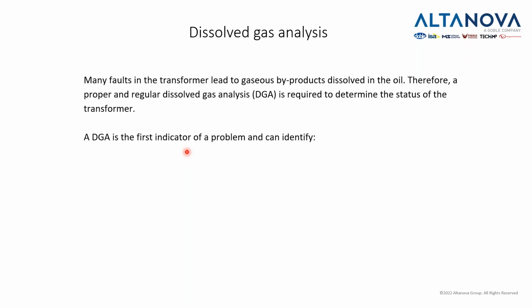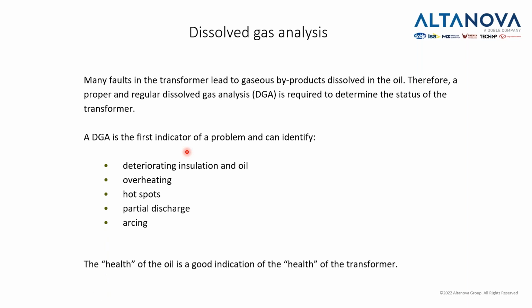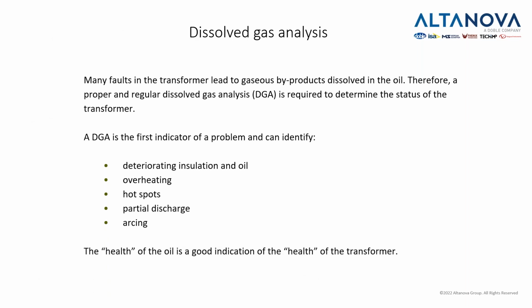One of the last topics, very, very important, is dissolved gas analysis. Dissolved gas analysis very often is the driver for further investigation of the transformer, because many transformers, not all of them, have oil inside as the cooling liquid, and also as the liquid which isolates inside the transformer. So if the transformer's oil is okay, then the transformer is okay. But if not, then the transformer might have issues. So DGA is the first indicator of a problem and can identify deterioration of the insulation, overheating, hotspots, partial discharge, arcing, and in general, it will tell you about the health of the transformer.